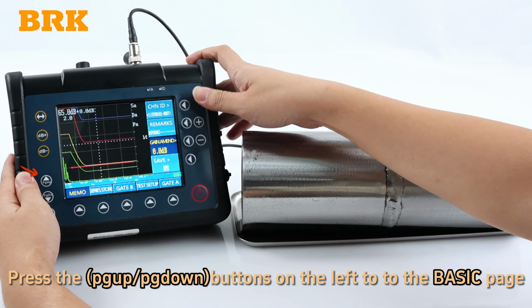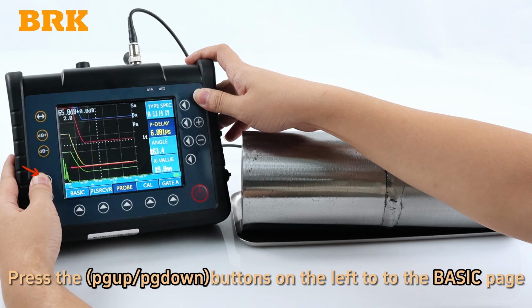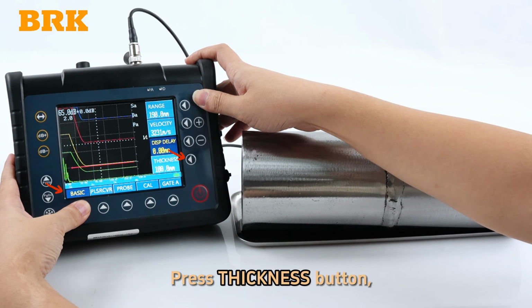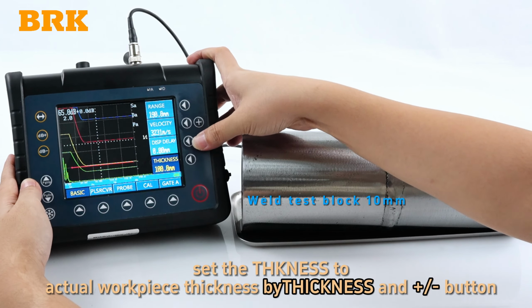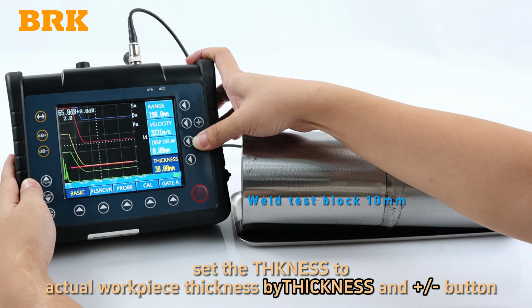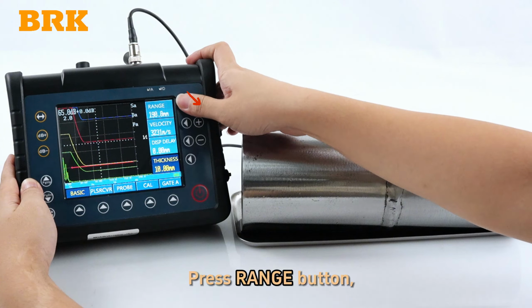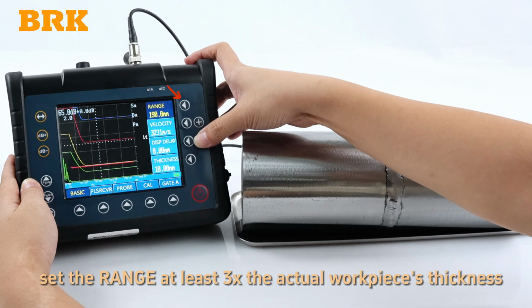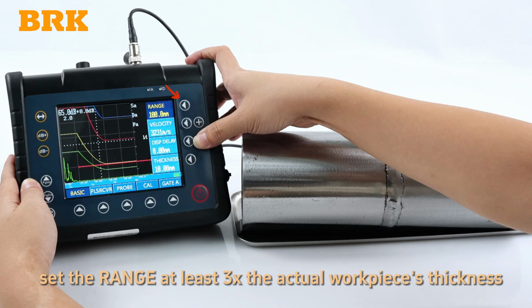Press the page up or page down buttons on the left to the basic page. Press the thickness button. Set the thickness to the actual workpiece thickness using the thickness and plus and minus buttons. Press the range button. Set the range to at least 3 times the actual workpiece's thickness.